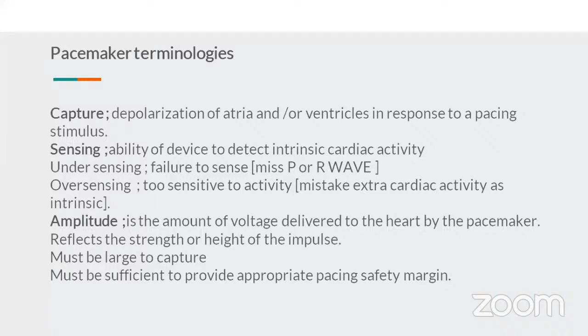Amplitude is the amount of voltage delivered to the heart by the pacemaker. It reflects the strength or height of the impulse. It must be large enough to capture and sufficient to provide an appropriate pacing safety margin. Pulse width is the length of time each pacing pulse is delivered, and it must be long enough for depolarization to disperse to the surrounding tissue.